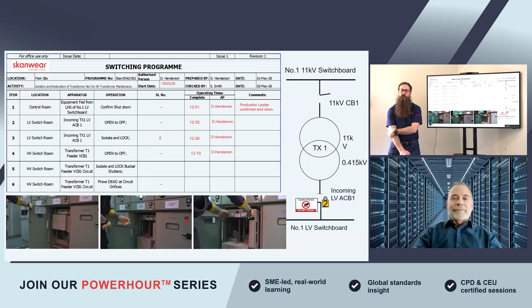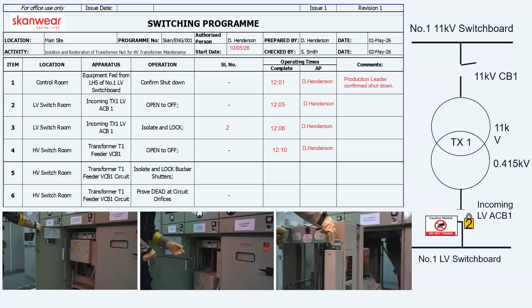So that was quickened up. That obviously took a lot longer to go through that process. In order to lock the shutters, we're now going to withdraw the circuit breaker. So I think when we're doing our outage and we've got limited amounts of time, all of this takes time, and we need to make sure we're being careful, we're being precise, and we're doing that steady process throughout to make sure we're all operating the switchgear safely.